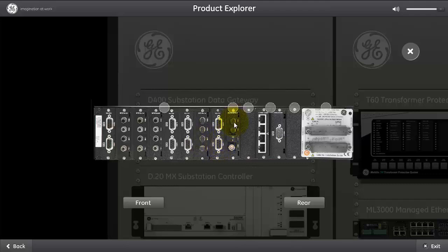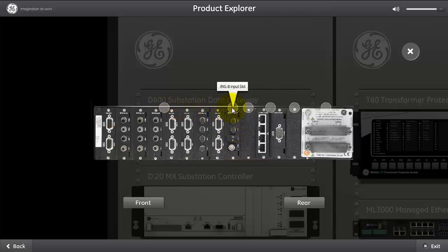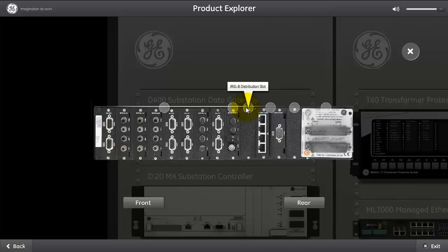The next card is the IRIG-B input to the D400. The IRIG-B input slot to the D400 is how we collect the time from the substation so that the events in the D400 are logged with the proper time. And the D400 has the capability of distributing the IRIG-B through the IRIG-B distribution slot.